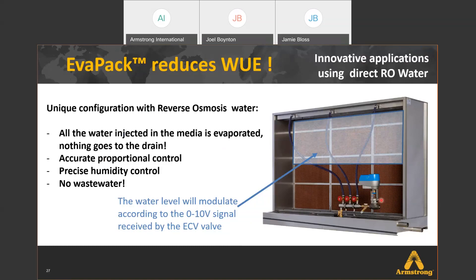Here's a picture of our ECV electric valve. The water level will modulate according to a 0-to-10V signal received by the ECV valve, giving a very tight turndown ratio of about 37 to 1, so we can control very tight levels.